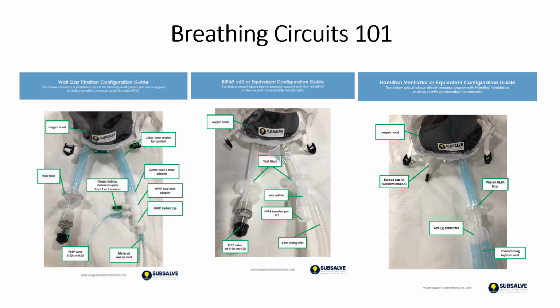So I went back to our test bench and did a little breathing circuit 101 testing. I acquired a number of different flow supply devices and started running tests. As it turned out, the breathing circuit itself varies quite significantly depending on what the flow source is, and that's a function of how pressure is controlled. Is it controlled at the machine versus at the hood with a PEEP valve or other restrictive orifices? It's a function of where supplemental oxygen is introduced. It's a function of where filters are in the system.